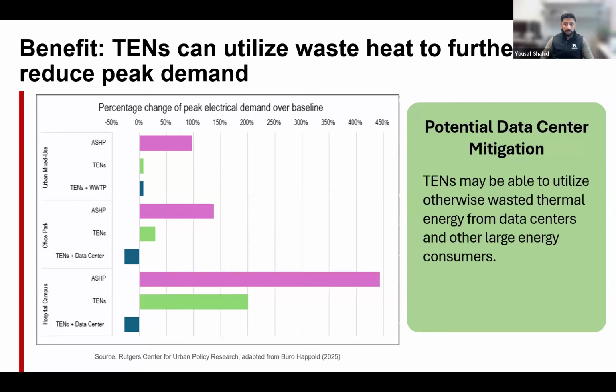But another important part that's easy to miss is that the integration of waste heat also reduces the peak thermal load, which determines how large the bore field needs to be in the first place, a very big capital investment decision at the design phase. So you're not just saving electricity, you're building less infrastructure to deliver the same results.